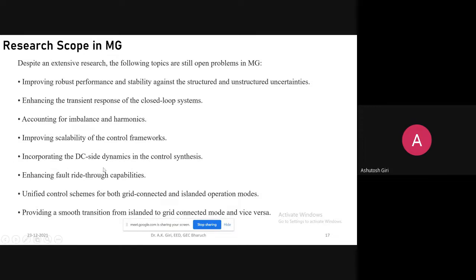You can design the control for that scalable system. Incorporating the DC side dynamics in the control synthesis - as we know, the DC side of the inverter should be stable. Otherwise, no desired response will be achieved. If we want to maintain proper active power flow, or balance the reactive power flow among various elements, it will be difficult to maintain. That's why DC link fluctuations should not be there in the system.